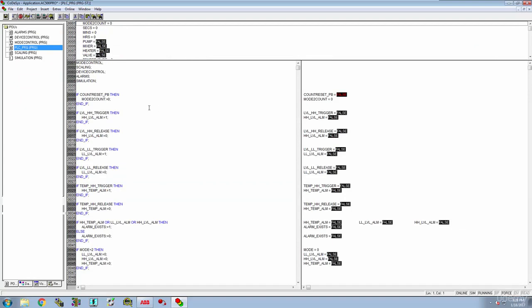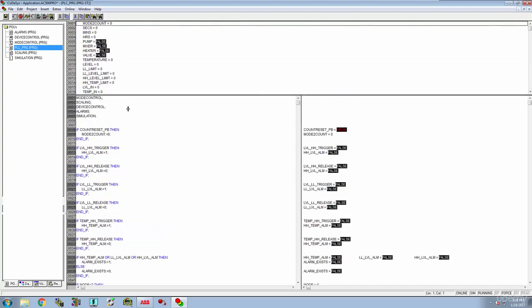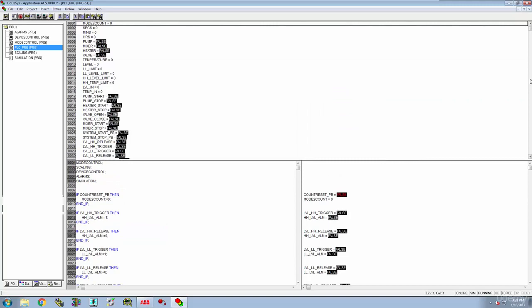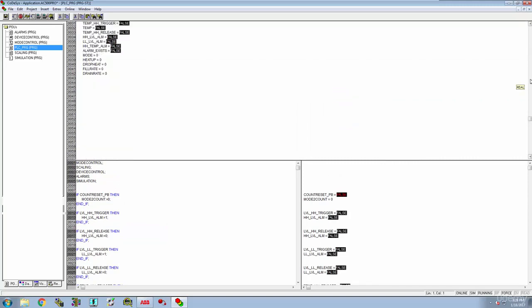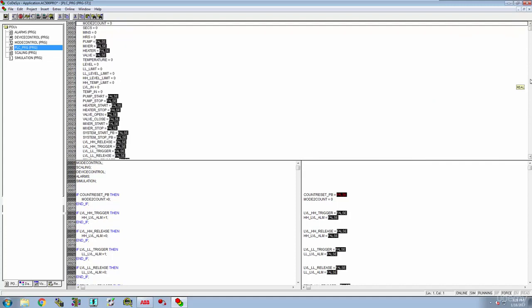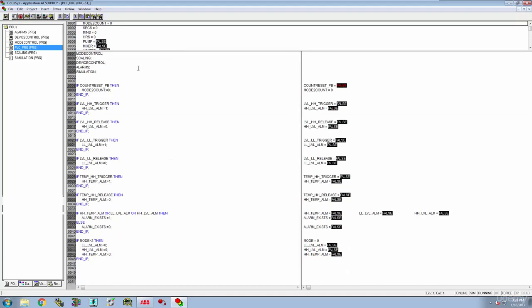Let's see why that didn't reset. If count reset push button, then mode 2 count equals zero. I'm showing mode 2 count in here and I'm guessing what that is — I've got mode 2 count defined as a local variable. So that's not a problem; if I come in here whenever we're offline I should be able to just remove that locally defined variable and we should be good. I've probably got the same thing still set up locally — we'll have to check.